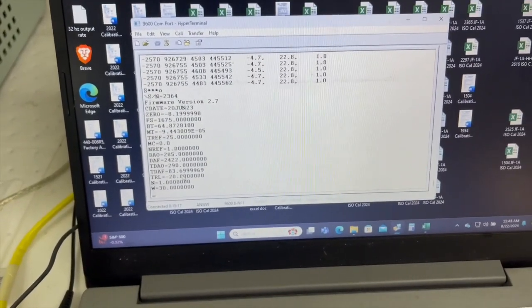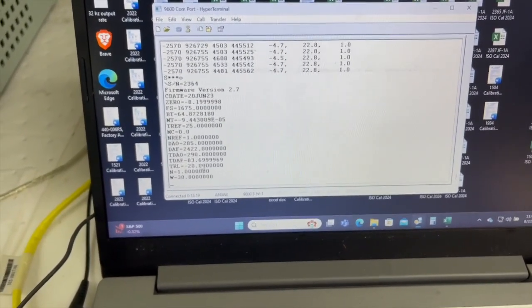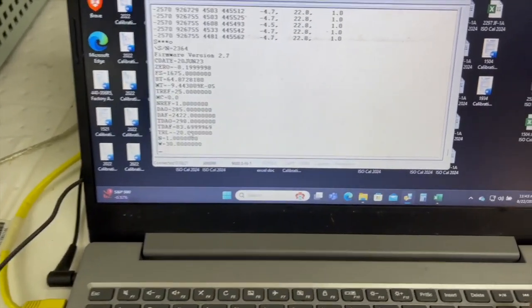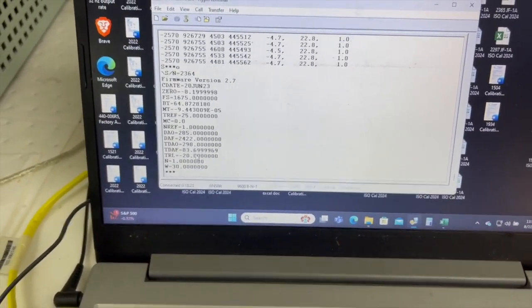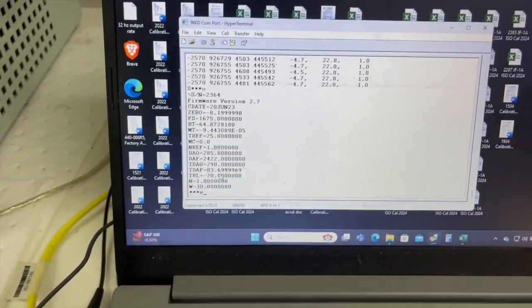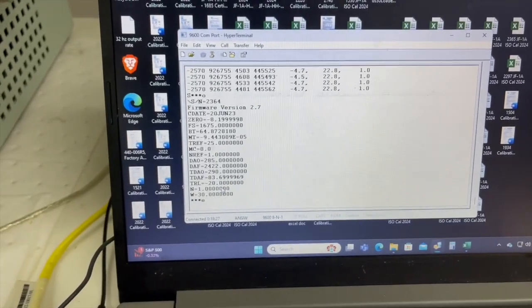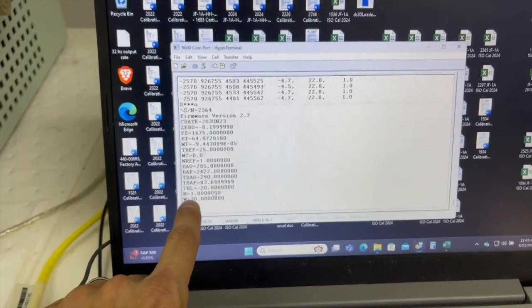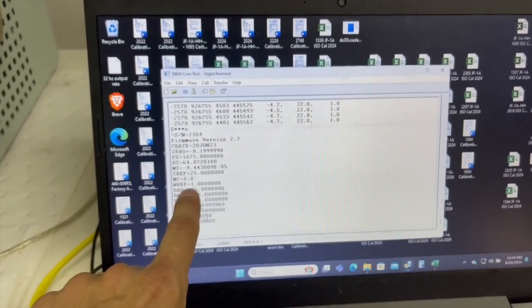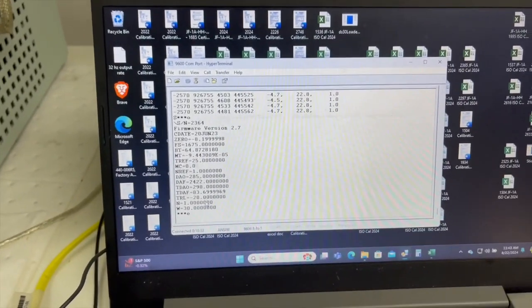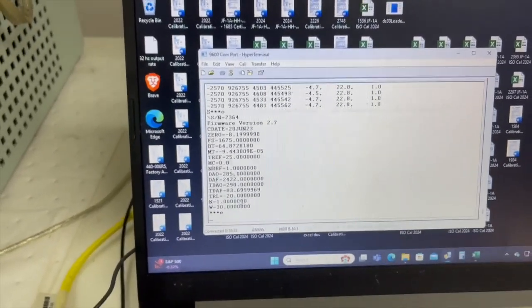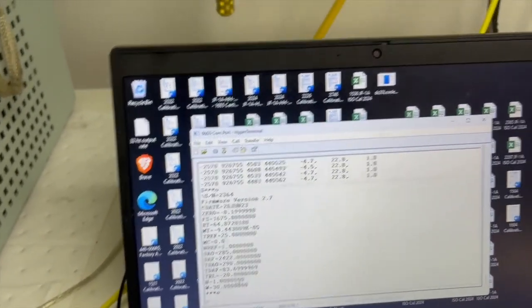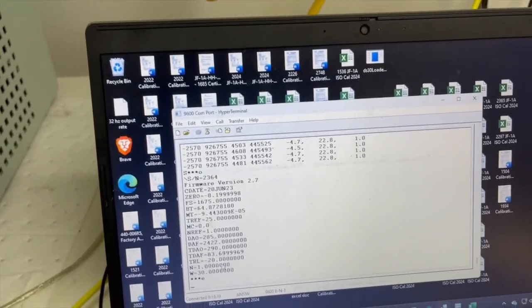Next step is to go into calibration mode. So you type ***E to save your RCal settings. You want to make sure that N equals 1 and NREF equals 1 before going into calibration mode, because you want to do instant work. You don't want it to be waiting for 3 samples at a time.